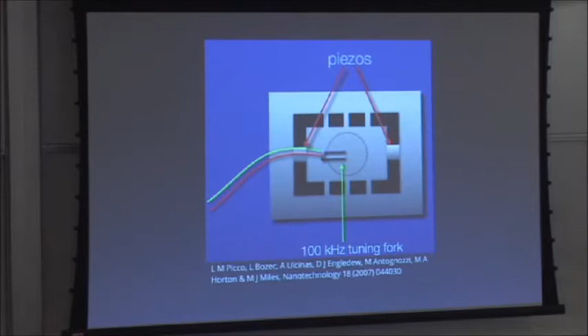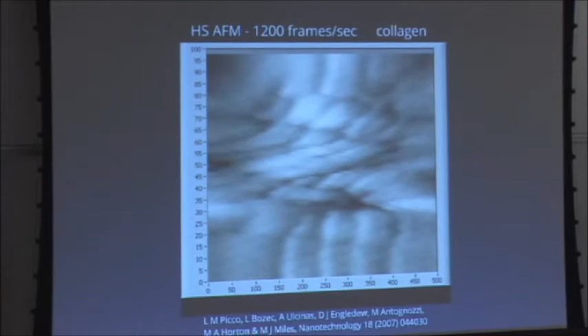Now we have to use our high-speed stage for the slow scan, for the frame rate, because 1,000 frames per second is faster than a normal scan tube will scan even a line. To do the high speed, we use another tuning fork that's 100 kilohertz, so we're doing 100,000 lines per second. And it still works. It's not pretty, but this is 1,200 frames per second of the collagen again, obviously slowed down. So if we have to, we know we can go sub-millisecond.